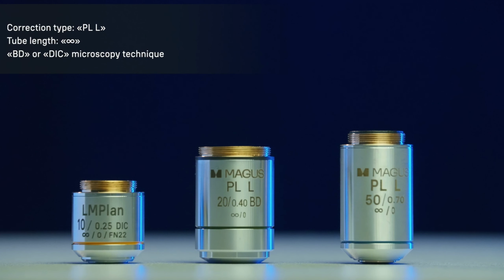The objectives are planar chromats with an extended working distance. The parfocal height is 45 mm and the linear field of view is 22 mm. The objective housing displays the following parameters: PLL, type of correction, planar chromat, long focus, magnification, numerical aperture, tube length, infinity, BD or DIC method. The color coding corresponds to the magnification according to international standards.